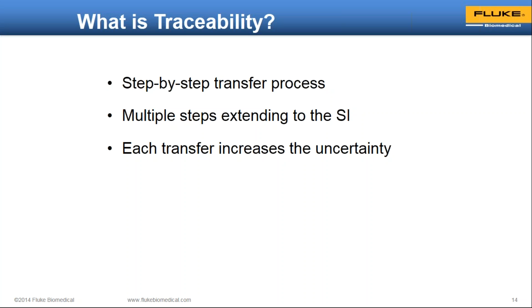Let me show you a concrete example and a short traceability path. At Fluke, at the headquarters here in Everett, Washington, we create the DC volt. We create that with a primary standard called the Josephson junction array. Once we have that primary DC volt created, we transfer it for use in our production lines and in our calibration laboratories for recal. The figures in blue are the uncertainty as we transfer that DC volt from the Josephson array to the transfer standards and on through this very short traceability chain.